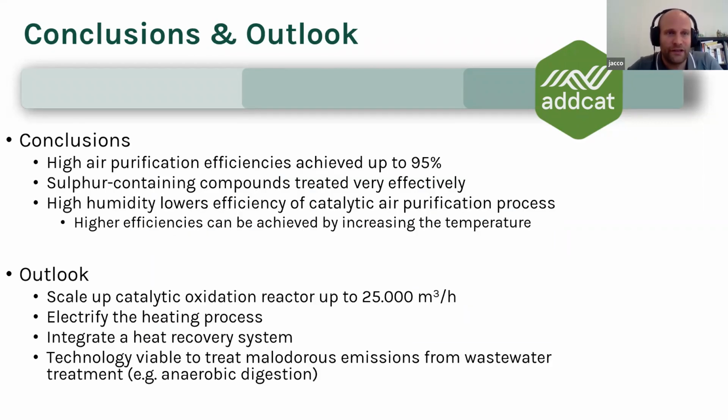So to conclude, we found a high air purification efficiency with this module in the field, with efficiencies up to 95%. The sulfur containing compounds were treated very effectively. And we've also found that high humidity, which of course you find in many cases, lowers the efficiency of the catalytic air purification process a bit.